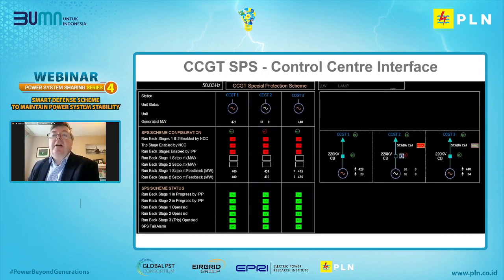This is just a view in the control center. It's probably difficult to see, but down the bottom, the green buttons are the scheme status, whether they're on or off. In the middle, if we're using runbacks, we can put in set points, which would be set up in advance. So we can automatically have the set points that the machine is to run back to programmed in. Then in the event of a loss of interconnector export, this can be triggered to run back to that level. Or we can also opt to trip the machines, so not wait for them to run back.